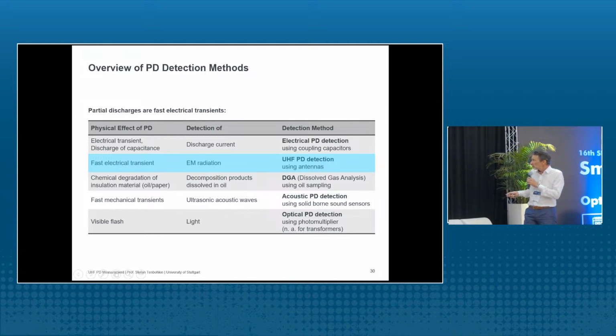Yeah, but of course you can also measure PD electrically, because if you have a discharge, also currents are flowing. Very small currents, but you can measure these currents. Additionally, if you have a discharge, also electromagnetic waves are emitted, and you can measure these waves by an antenna, of course, like we have it in our mobile phones, or here is a microphone. And also acoustic waves are generated. Yeah, as I said before, if you're standing under a transmission line, you can hear the corona. Yeah, same in a transformer. There are noises generated, which you can measure by microphones on the tank wall.